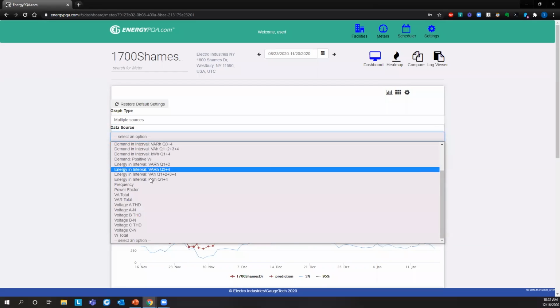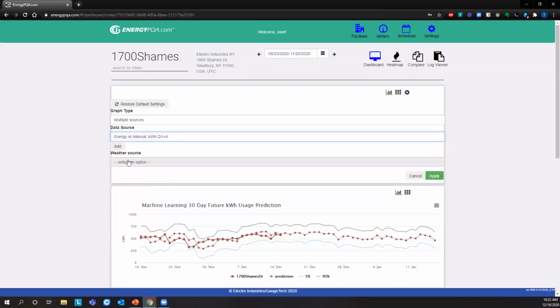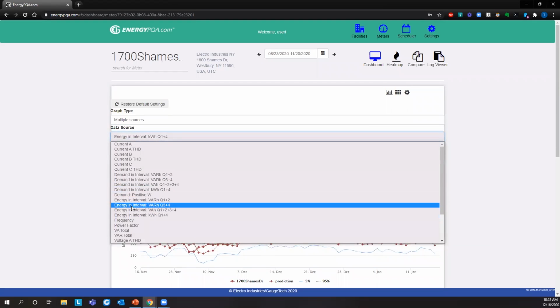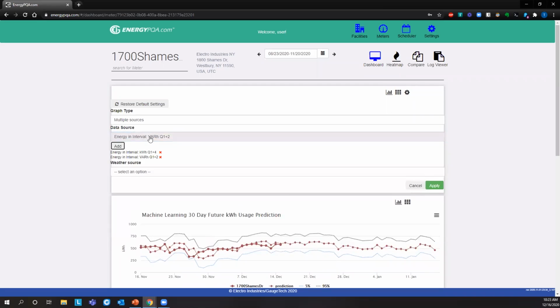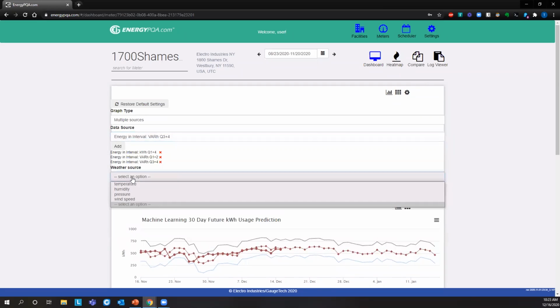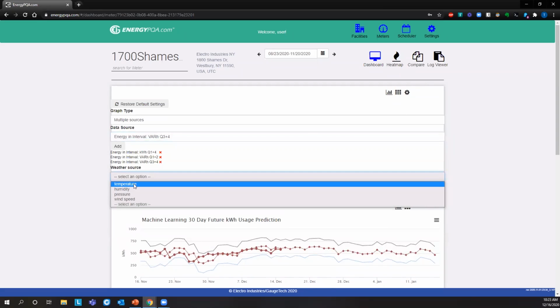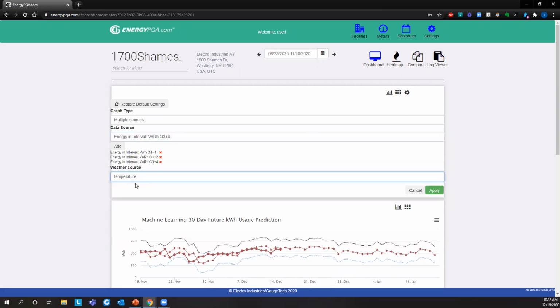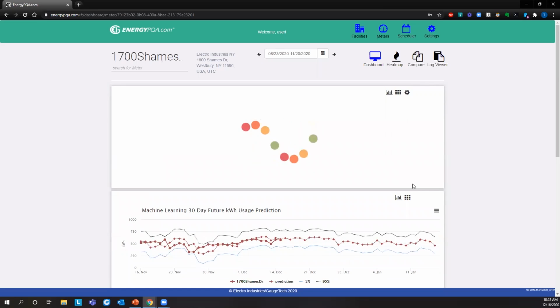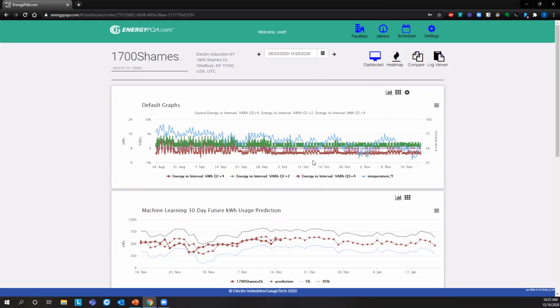We can change this to look at energy in the interval. If you wanted to view your kVAR readings, we could look at that. We can also trend temperature, humidity, or pressure. So if you had a day where you had a really high spike in usage, it might have been a really hot day where cooling was running more. So now I have energy, var hours, quadrants 3 and 4, and temperature.